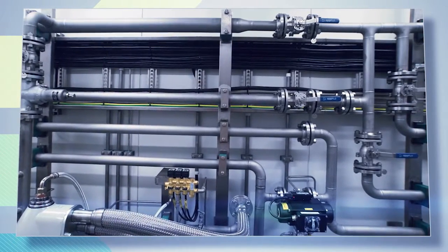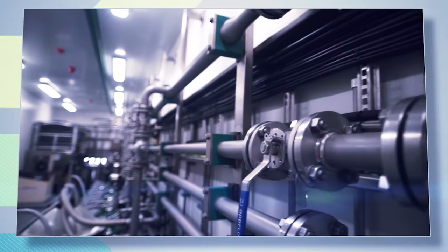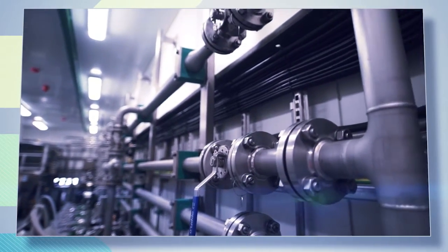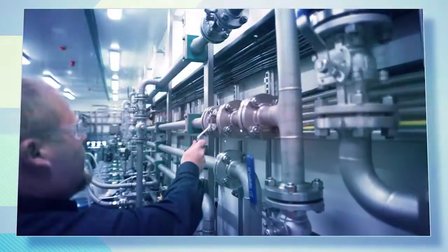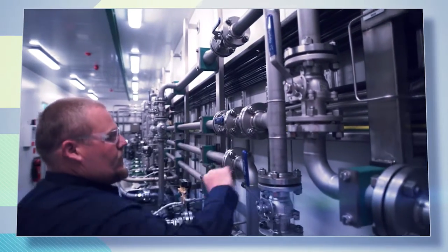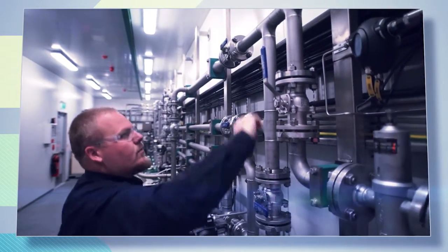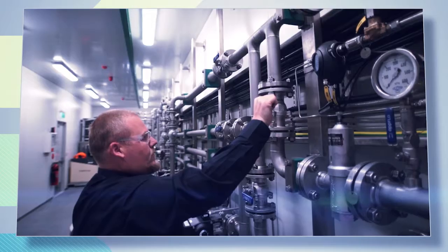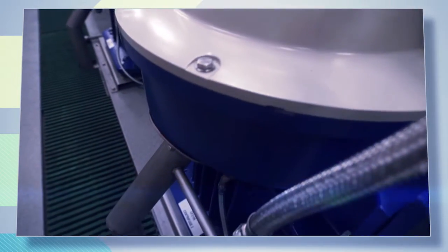A bypass line and valve has been incorporated in the fuel block to facilitate line flushing and closed-loop fuel treatment. When the valve is open, fuel will circulate from the raw fuel tank through the centrifuges to the clean fuel tanks, to the last chance filters and back to the raw fuel tank.